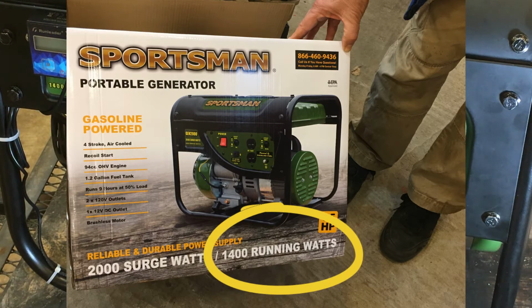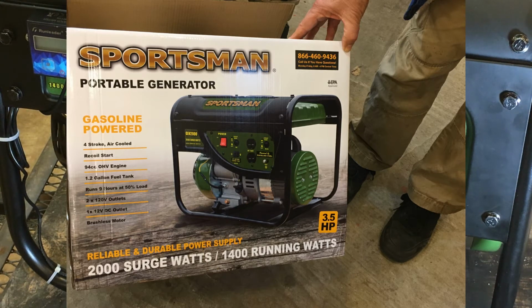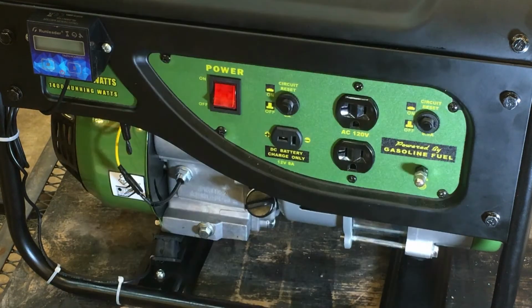I certainly could not get the unit to run at 1400 watts. I did drop the load down to about 1250 watts, again using the heat gun at low setting plus a 500 watt quartz floodlight, and it still couldn't carry that load. The throttle on the engine under either of those loads was fully open — nothing left, it couldn't be opened any further to get more engine speed out of it.